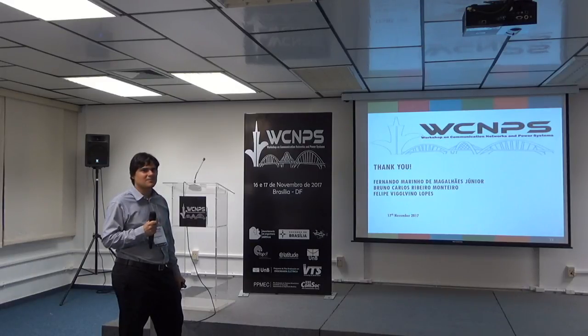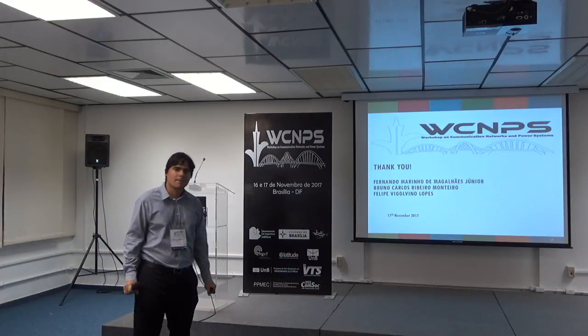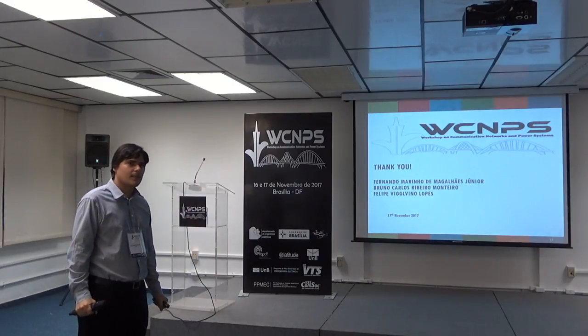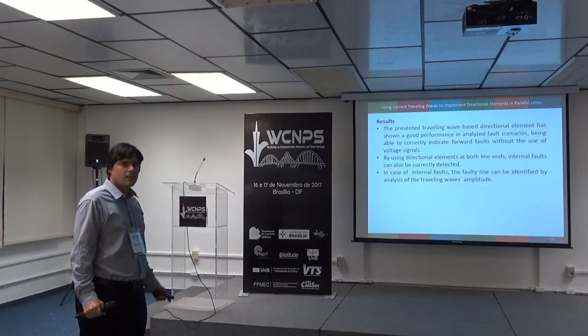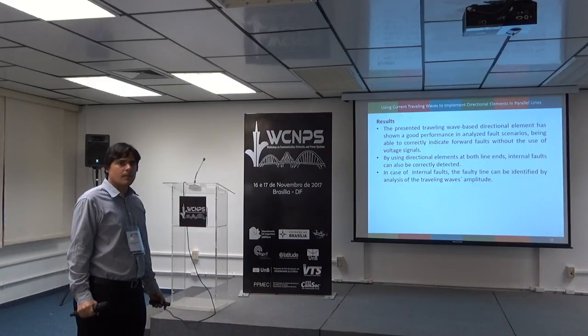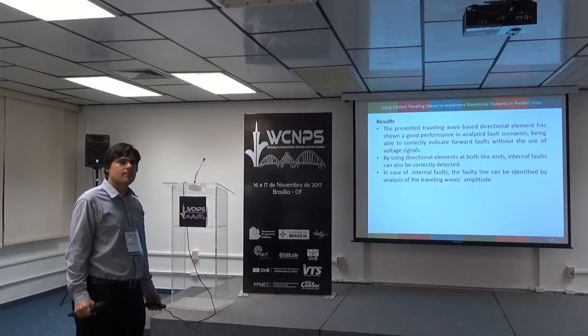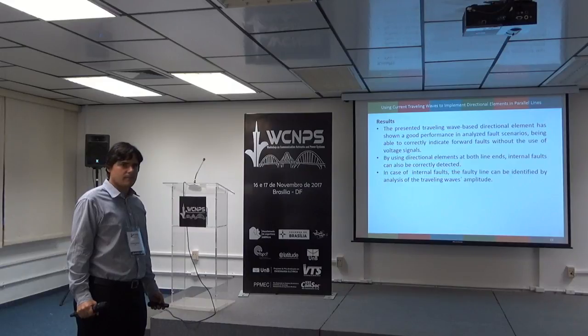Excuse me, I just want to present a brief clarification about what Fernando has just talked about. In fact, we have to use some models to simulate communication channels, but we already have some functions working using dedicated fiber optic links, and in this case the latency is almost deterministic. So to simulate this kind of link, we just have to put a delay on the communication timestamps, so it's easy to perform. But in this case, we just use the signal separately from each line terminal, so we do not have to analyze timestamps, and synchronization is not required.